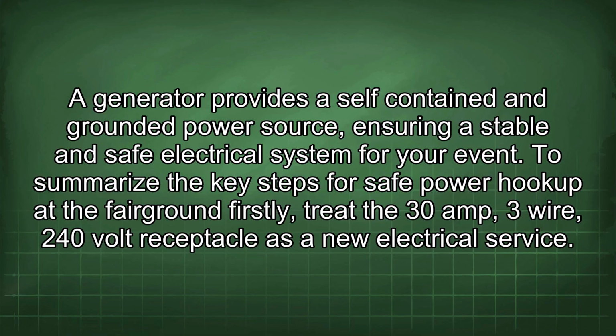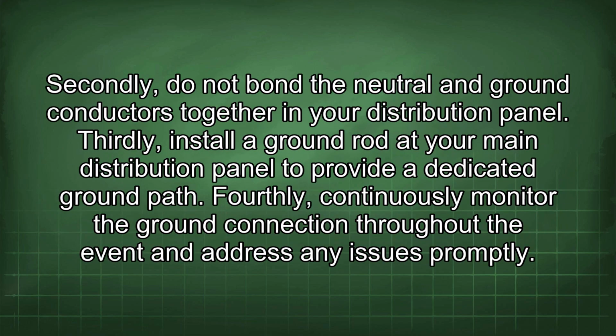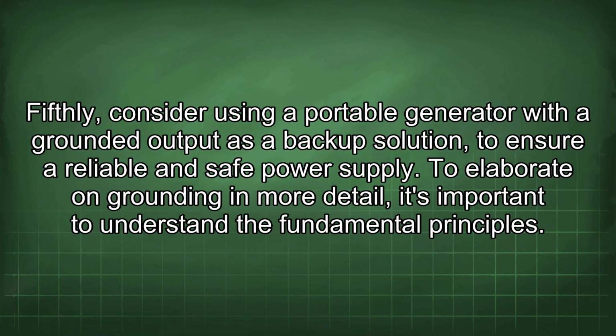To summarize the key steps for safe power hookup at the fairground: firstly, treat the 30-amp 3-wire 240-volt receptacle as a new electrical service. Secondly, do not bond the neutral and ground conductors together in your distribution panel. Thirdly, install a ground rod at your main distribution panel to provide a dedicated ground path. Fourthly, continuously monitor the ground connection throughout the event and address any issues promptly. Fifthly, consider using a portable generator with a grounded output as a backup solution to ensure a reliable and safe power supply.